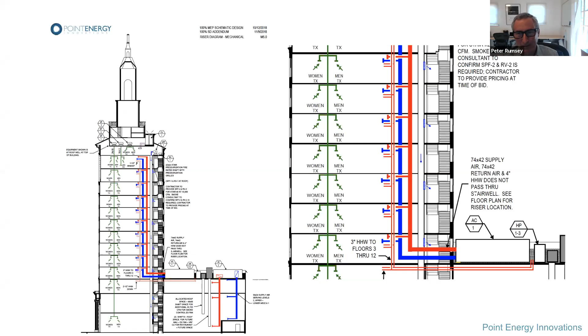That VAV system is very much a mainstream system, but it will be fed with reheat coils, and those reheat coils will be fed with hot water created from a heat pump. So it's a very standard system where we're just swapping the boiler out for a heat pump. The heat pump is an air source heat pump, going on the roof, and it will seamlessly integrate into what's very much a standard system.